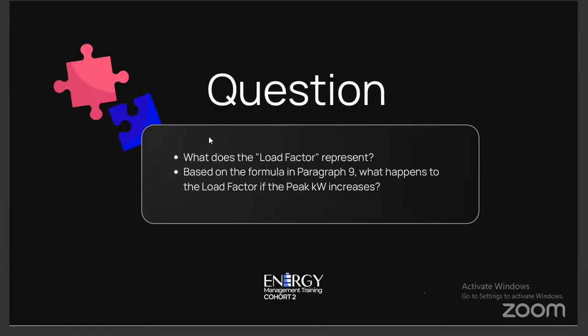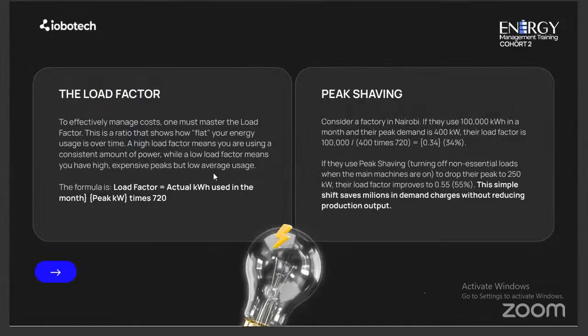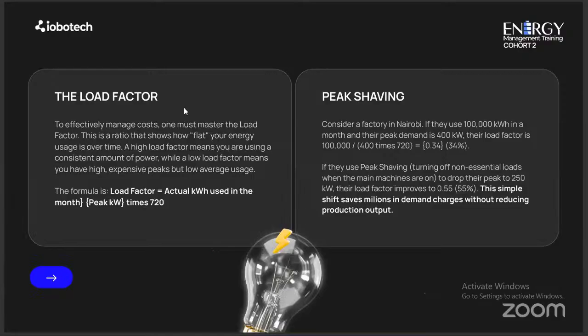So the two questions are about what the load factor represents and what the peak kilowatt increasing would do to the formula. The load factor represents how much money you're going to have to pay. If your operations include a peak power usage while you have a very low average usage throughout the month, that's going to give you a very low load factor. If you have a consistent load, then you're going to have a high load factor. You want a higher load factor at all times, because that means your billing is going to be consistent with your actual usage rather than being based off the times when you have very high loads.